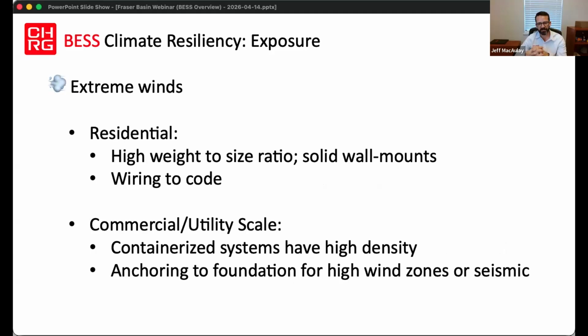Some applications are outside, even at a resi level, and just mounted to the wall. But because they're so heavy, you're physically attaching it into something really solid, attaching it to the studs through the external wall, through very robust mounting techniques. Because the amount of wind exposure on the battery is relatively little and the weight is relatively large, and therefore the mounting is very solid, I don't think it's a major risk on the wind front. Wiring is more of the risk typically, but in Canada they're going to make sure things are secured.